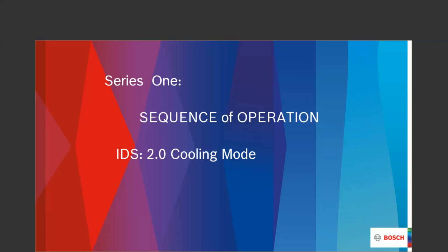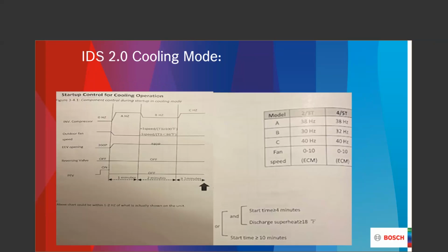What we're going to do is look at the cooling mode of the 2.0 first. And I've got 3 slides in here that I'm going to apologize one time for. This particular slide is a picture that was taken, and I tried very hard to find a better way to get it to you, but I just can't. So when we're looking at the cooling mode operation, we're looking at a call from the thermostat, the controller, whether it's yours or mine. We're looking for that Y call, and we're going to get 18 to 28 volts coming out there, and it's going to basically tell our unit to come on in the cooling mode.